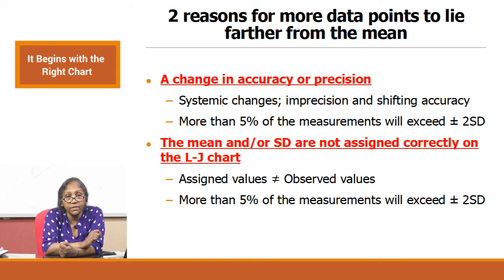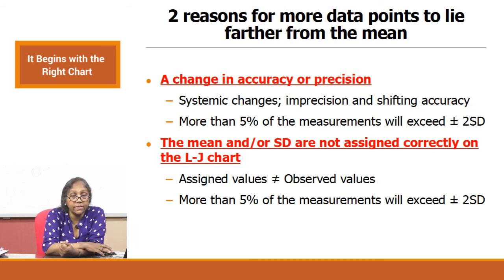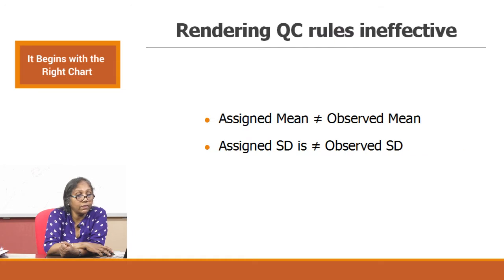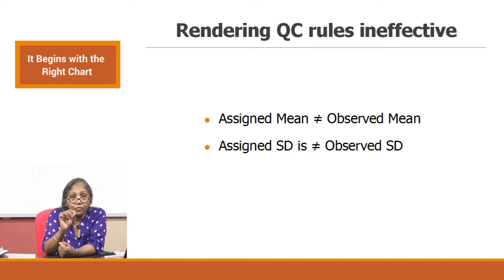The manufacturer's mean and SD are assigned on the chart, which may not be suitable in your laboratory because the mean you are observing could be different from the mean that has been assigned. Similarly, the SD you have put in may not match the SD you are observing. These are the two main reasons which render QC rules ineffective: assigned mean not the same as observed mean, and assigned SD not the same as observed SD.